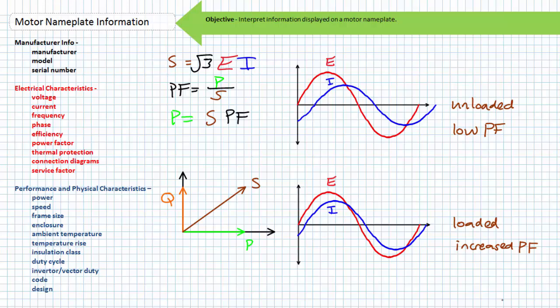the frequency of the AC system this motor is intended to run on. All the other data on the motor nameplate is based off this fact. A 50 Hz motor with a rated speed of 1,460 RPM won't spin at 1,460 RPM when operated at 60 Hz, but rather around 1,750 RPM.